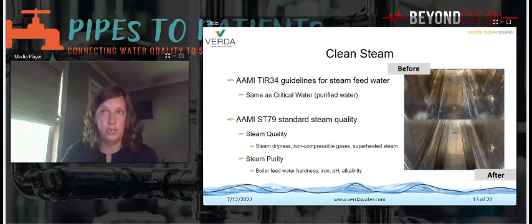But even with ultra-low water hardness, feed water that's high in total dissolved solids and chlorides can still cause problems for instrument reprocessing. Staining, spotting, corrosion, wet packs, and incidents of bioburden are common challenges in sterile processing and are due to the quality of the sterilizing steam, which depends on the quality of the steam boiler's feed water. There's a long history in healthcare for the chemical treating of boiler feed water, incorporating steam filters, scheduling of boiler blowdowns to maintain the boiler equipment, and produce clean, dry steam.